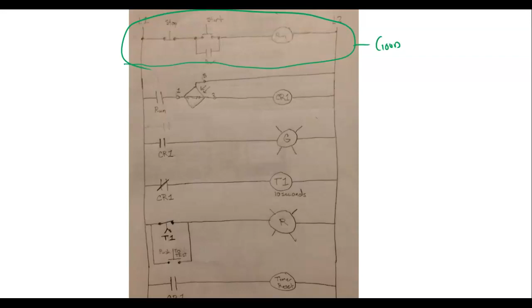This one looks impressive - this is really good, because the way everybody else worked, you had no way to turn this sucker on or off. Here, when the person came in, they did put a start-stop station so they could come in the morning and turn their car wash on and off. So that's good. Sensor looks okay. They've got a run contact right here - normally we would put a run contact in every one of these circuits, because what would happen is the green light would be on, right? You understand that?